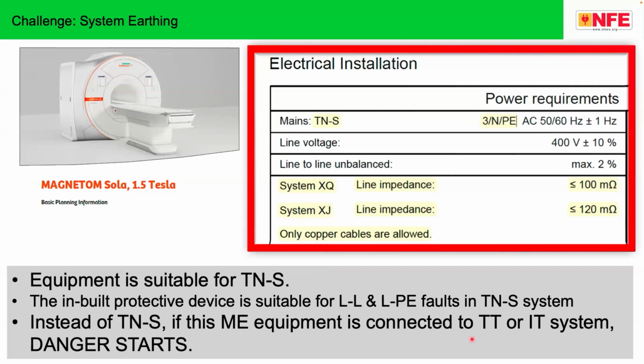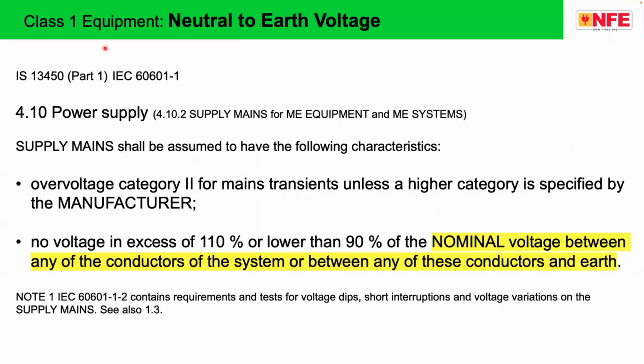If equipment designed for TNS is used in a TT or IT system, you forget. Equipment may work for several years, but once there is a fault, you will be in disaster. Please don't do it. Another challenge which we face is a biomedical equipment manufacturer coming with an argument of neutral to earth voltage. More than 2 volt, 3 volt or 5 volt between the neutral conductor and earth conductor, they say my equipment fails, which is absolutely wrong.